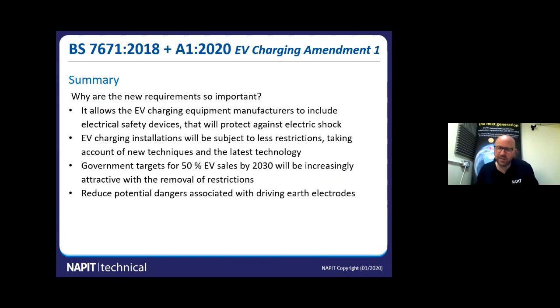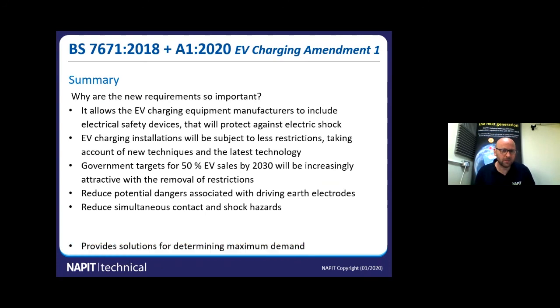I briefly mentioned CAT scanning earlier. There's always that concern that you're going to drive through a gas pipe or an electric cable when you put an electrode down, especially a rod. Okay, so we've got fewer dangers there. Simultaneous contact: if we're using a TT earthing solution, we need to be aware that there's no simultaneous contact with another earthing system. If there is simultaneous contact between two earthing facilities, we could have a potential difference and receive a perceived electric shock. So this is going to be reduced if we use these new techniques that are in the charge points.